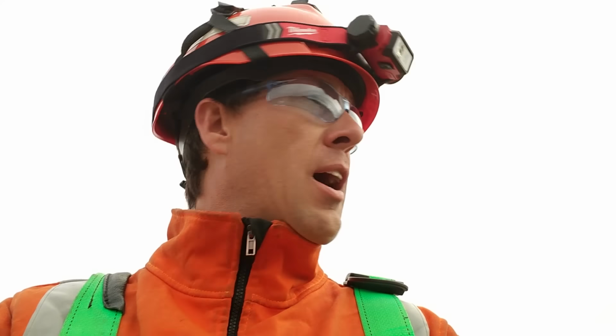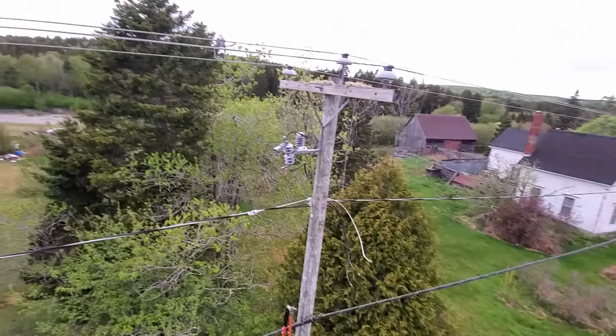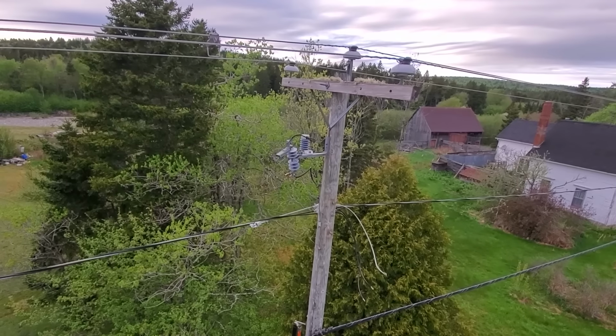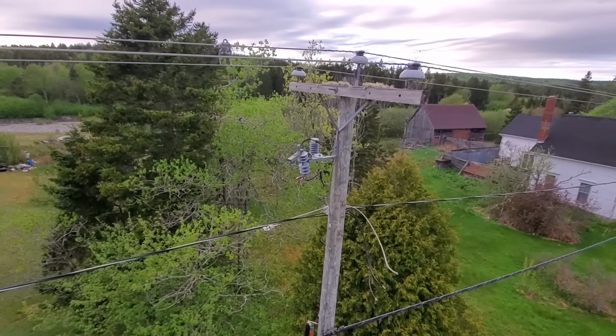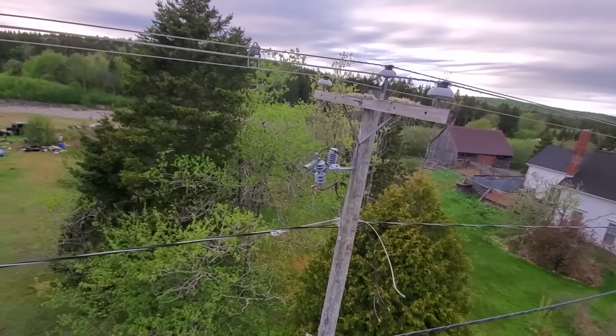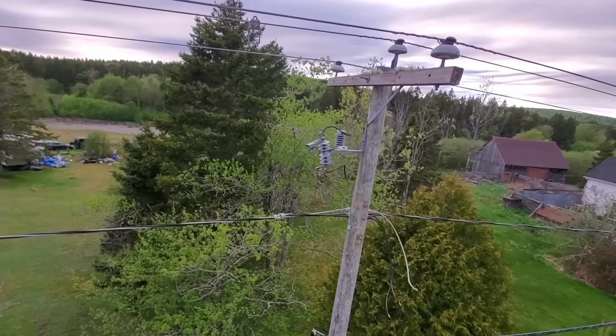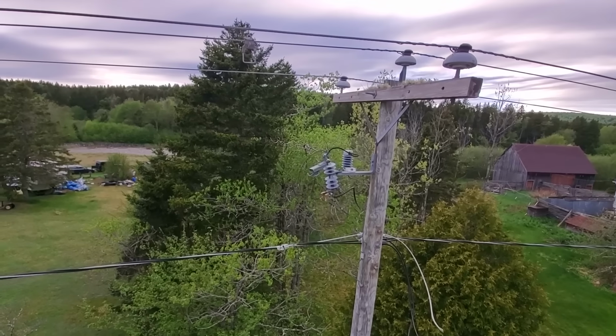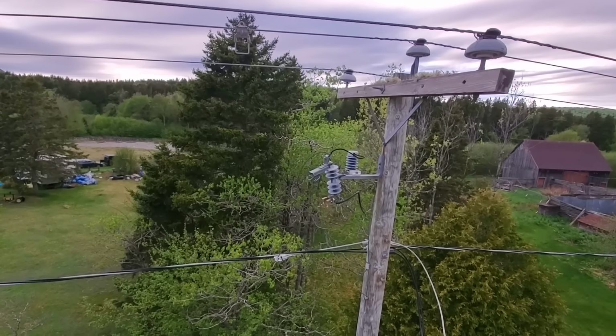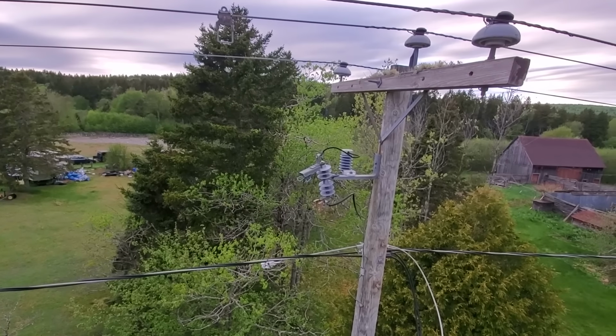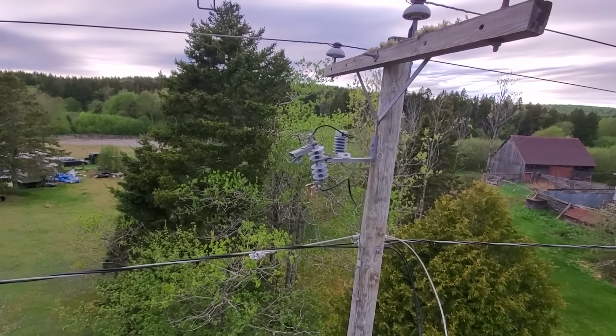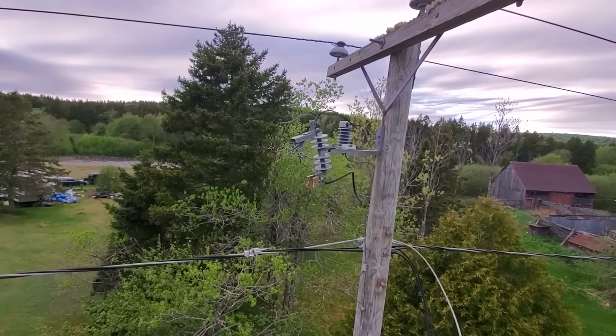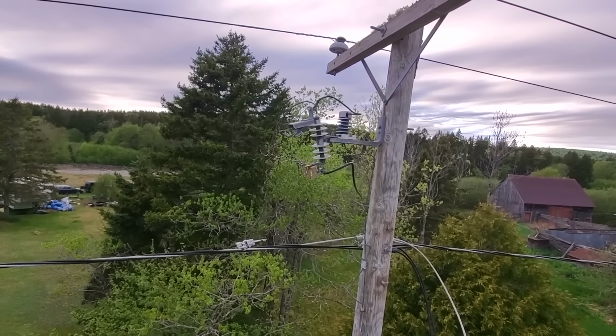So the older style, let's take a look at the lightning arrestor again. When you're tapping that lead on and you're 6 feet away, if that lightning arrestor is bad, which is not common, but if it's bad and it blows up, it's not fun to be anywhere near that. So the newer style transformers, the lightning arrestor is on the transformer, and it doesn't become energized until you actually close in that cutout.